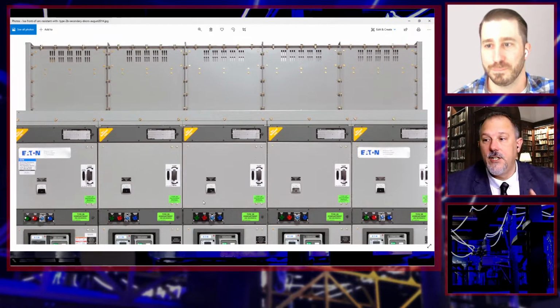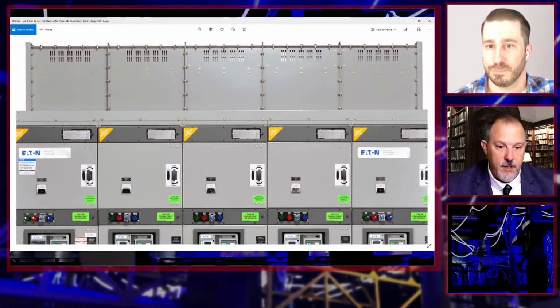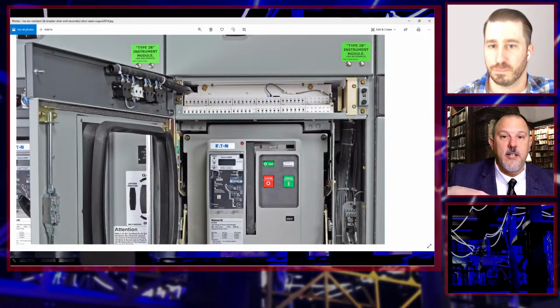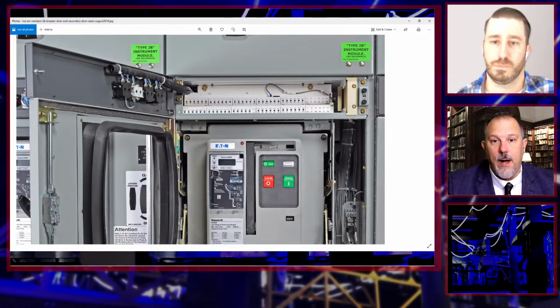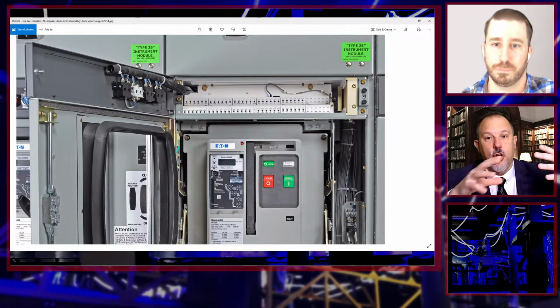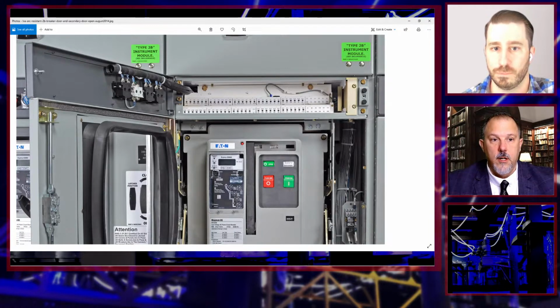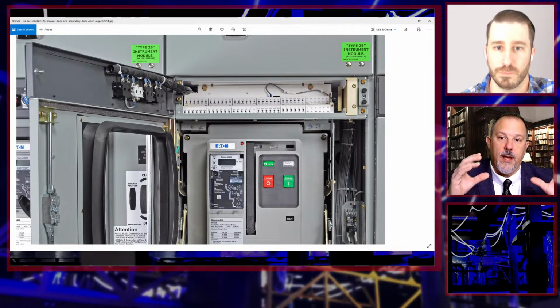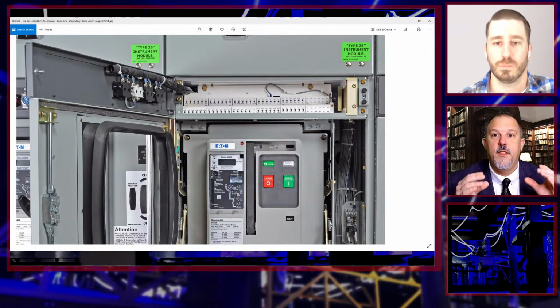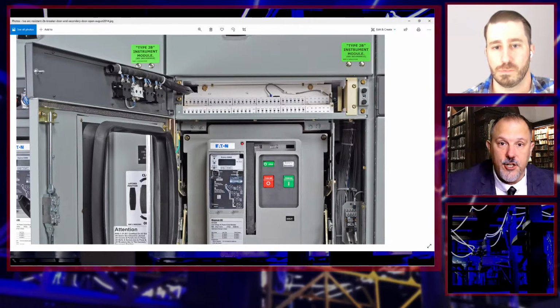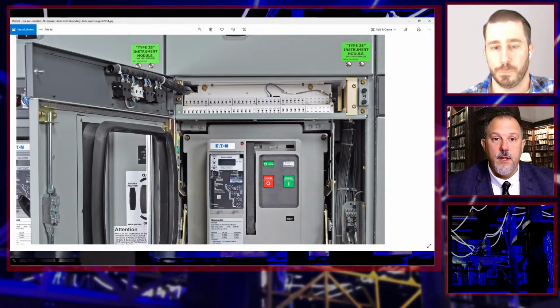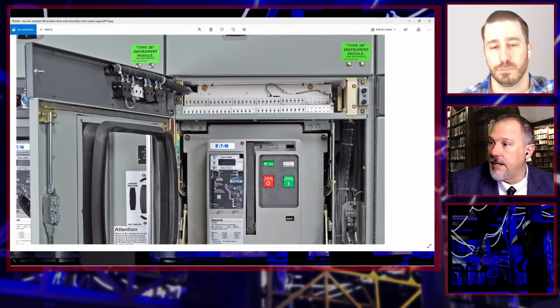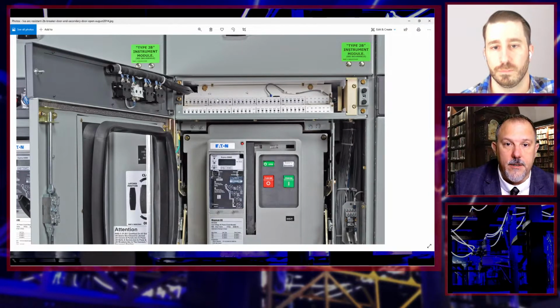Now, to your point, when you talk about needing to work on this, you're going to have control wire, right? So you may be able to close the door and just open a door to a compartment that, the way it's tested, like in a 2B construction, the arc won't propagate into that low voltage compartment, so you're protected should something happen while you're doing some work — I guess that would be this top area right in here.